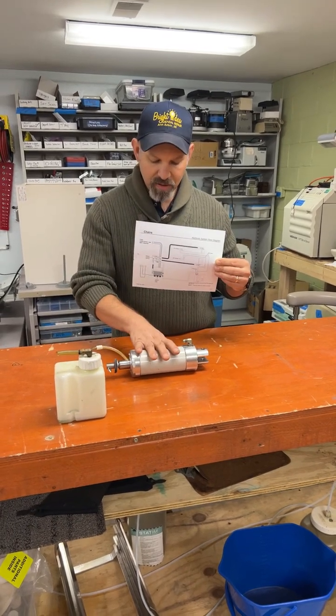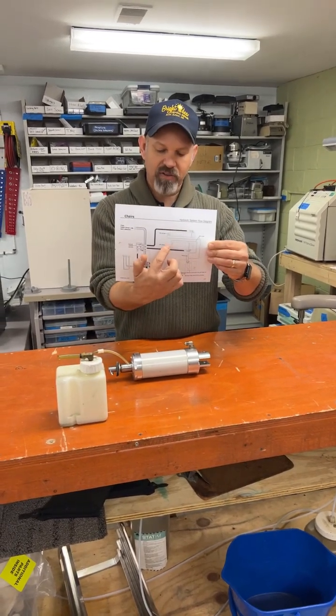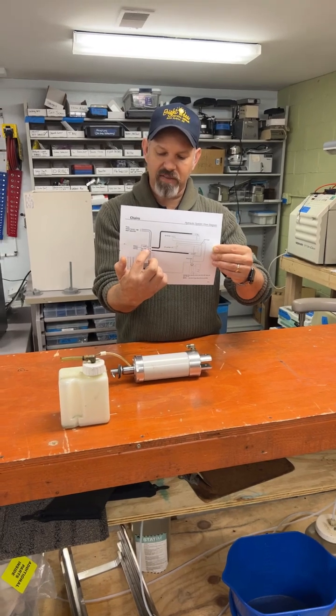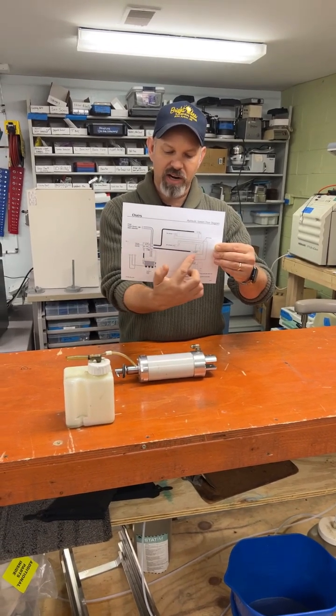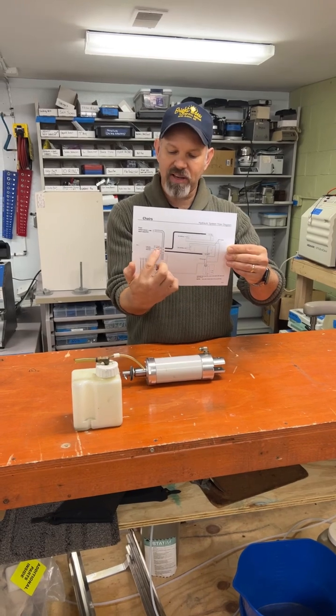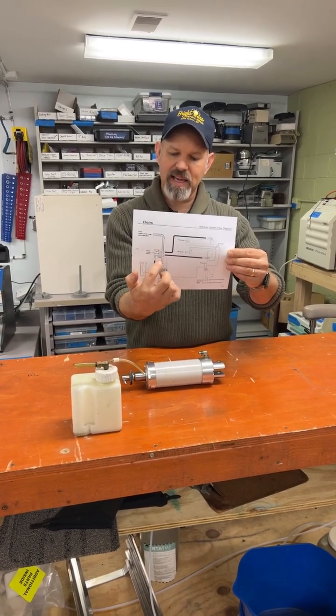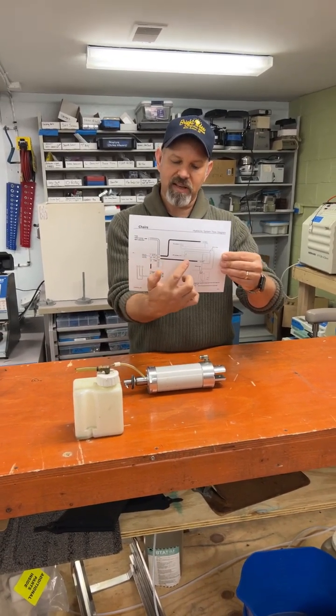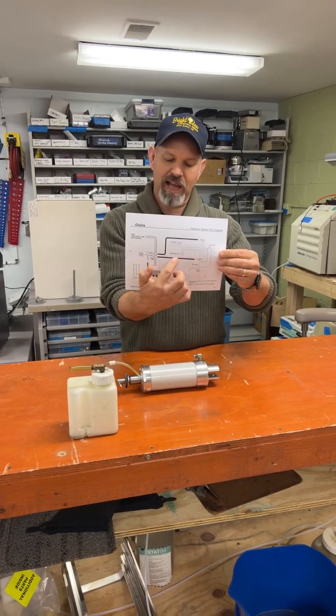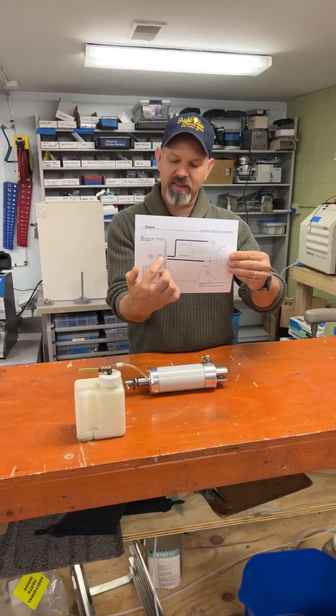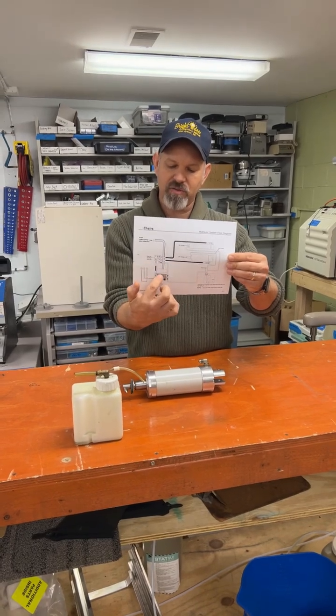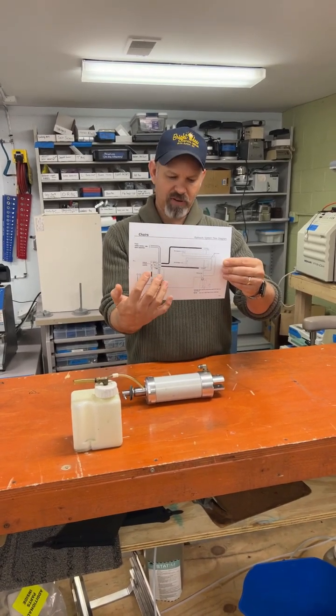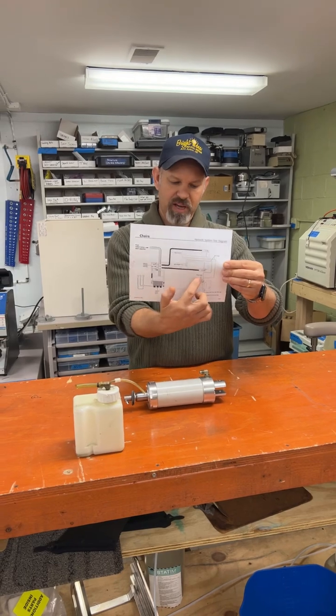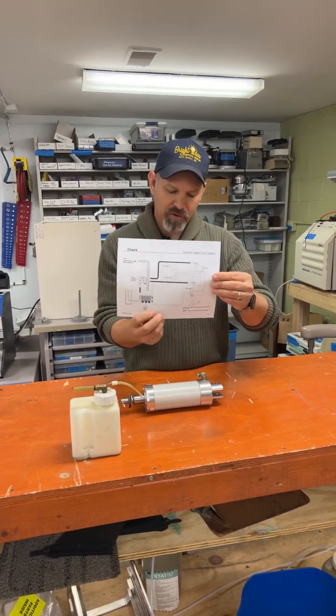This cylinder is single acting, so when you want to lower the chair, this line is opened at the manifold, and the fluid is allowed to go back and vent into the reservoir, which is over here.